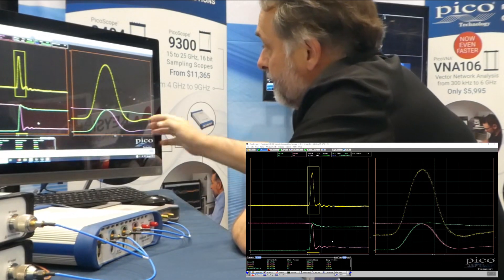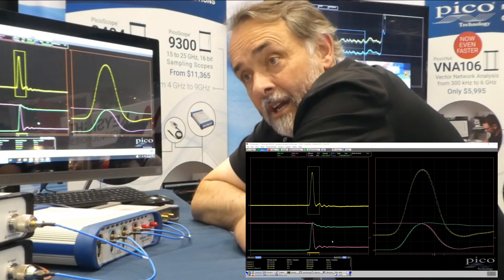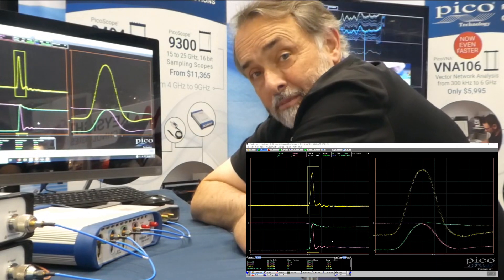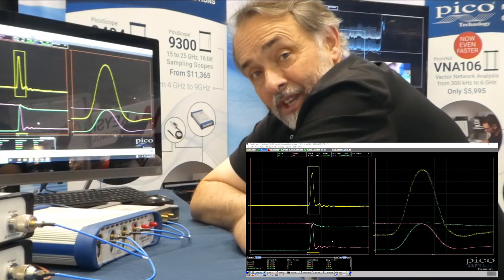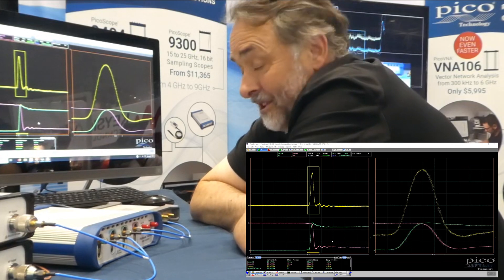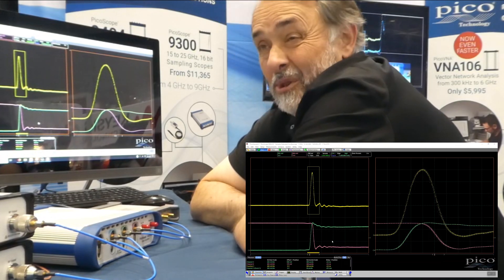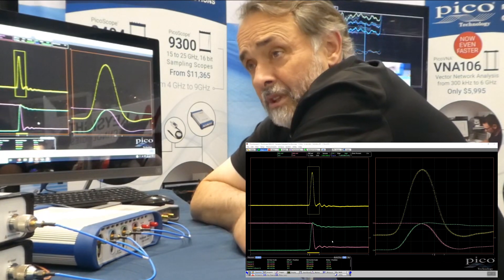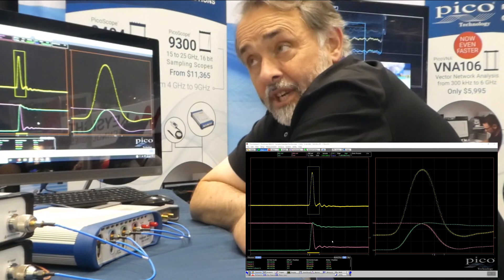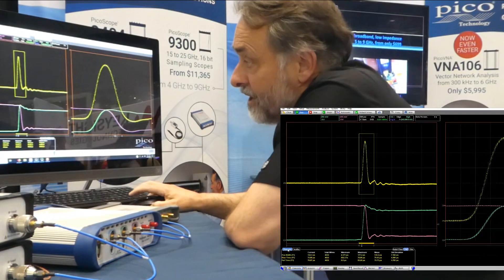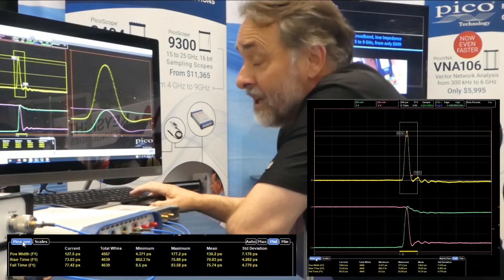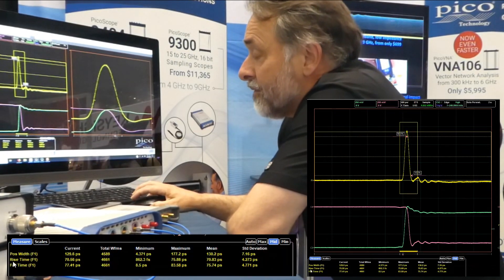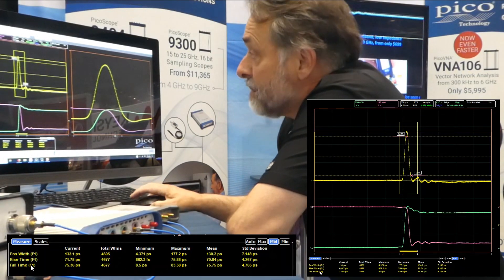What we're looking at is 50 picoseconds per division. We're sampling that waveform at one tera sample per second, and as you can see we're doing that with really quite low jitter — jitter of the order of one and a half picoseconds RMS typical, so it should be less than 1.8 guaranteed. I've got positive width, rise time, and fall time being measured for this pulse.